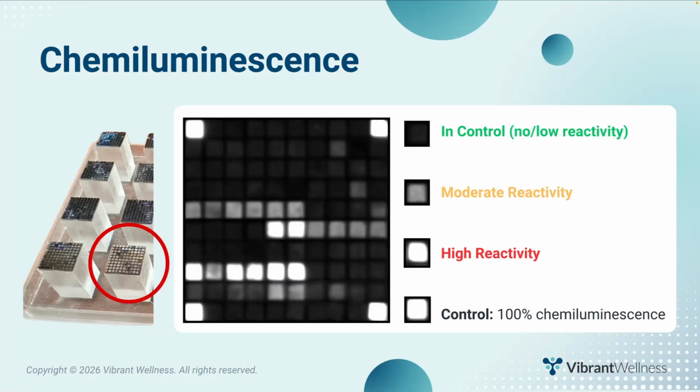Finally, a high-resolution imager is used to simultaneously detect chemiluminescent signals from labeled antigen-antibody reactions at each microchip throughout the multiplex microarray. Again, each pillar can measure up to 100 analytes because it is a 10 by 10 grid. Amplified chemiluminescent signals with high signal-to-noise ratio provide high sensitivity, meaning very few false negatives. In summary, this automated process allows for high throughput, sensitive, and specific analysis of multiple biomarkers for minimal sample volumes.